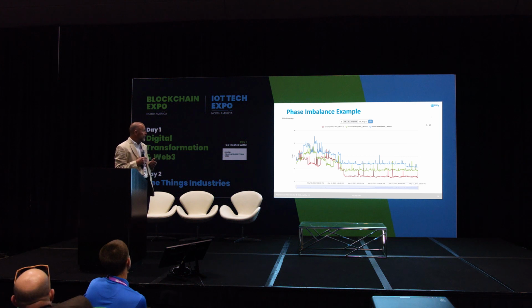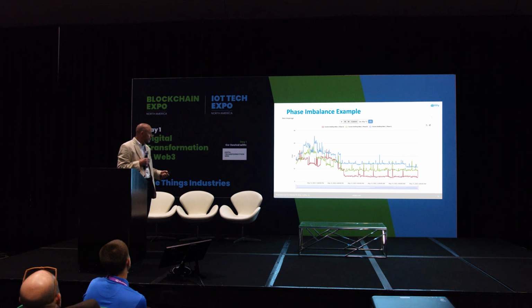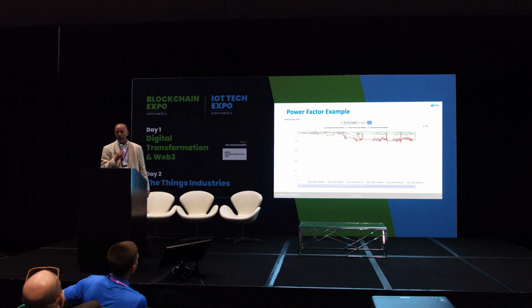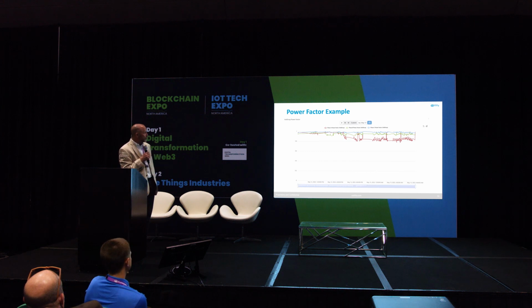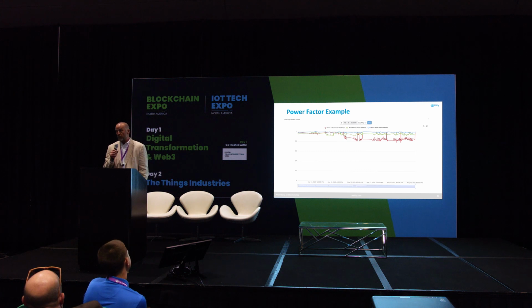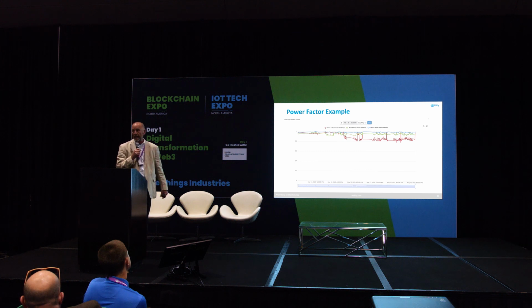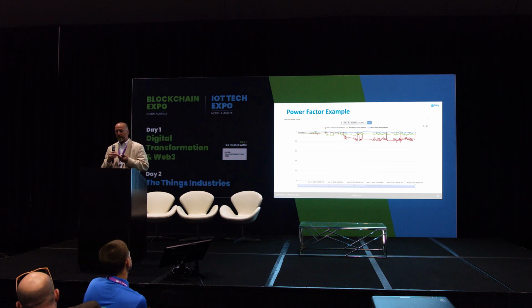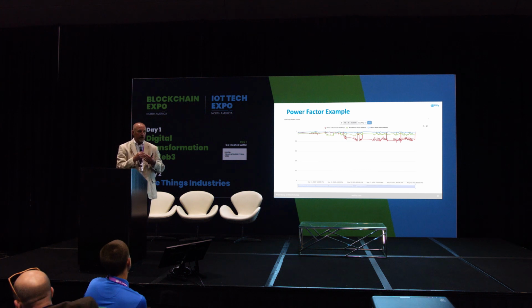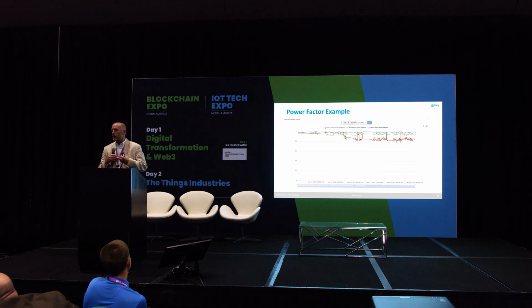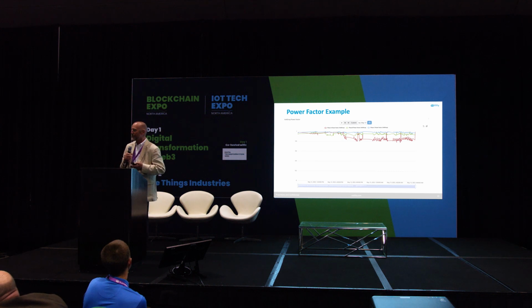Also within that building, we have a volt drop, and this is showing the power factor. Rocky Mountain Power charges more when your power factor drops below 0.9, and you can see this one is dropping below 0.8, so they're definitely paying more because of this power factor. When the consultant comes in, he's going to look at what it would take to remediate this issue. Hopefully, when I come back next year and present, I'll have the results of this to share with you, or at one of the other conferences coming up.